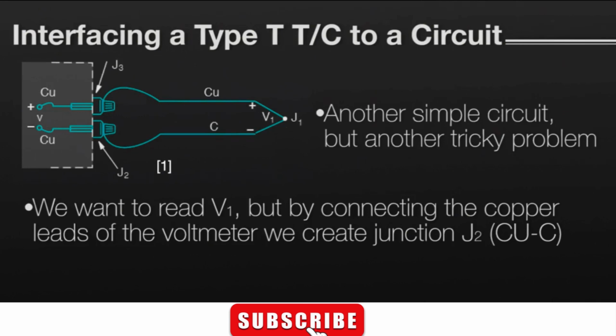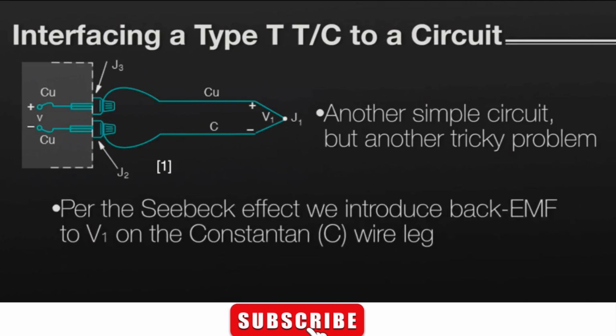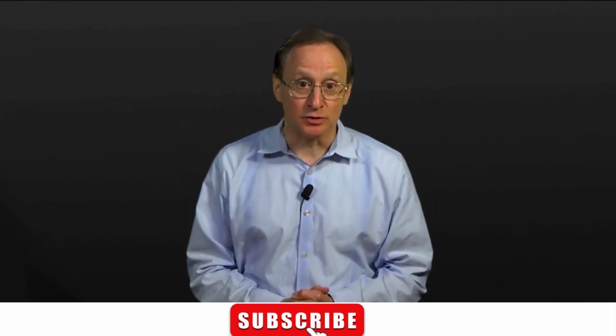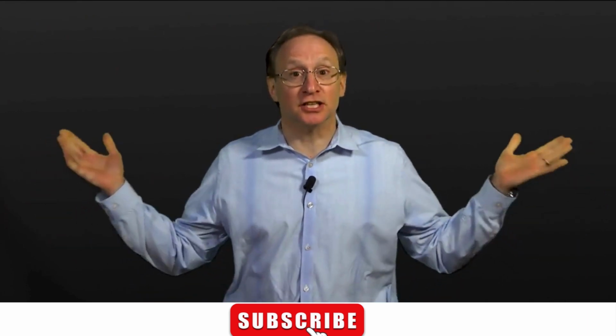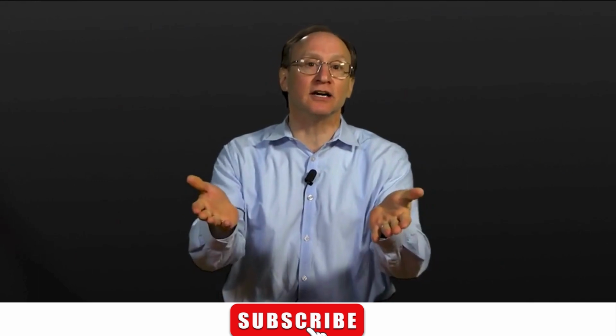We connected the copper and Constantan leads to the copper terminals of our voltmeter, and oops, we created another junction of dissimilar metals where the Constantan lead meets the copper terminal at junction J2. So what, you say? Well, here's what. You just introduced a back EMF thermoelectric voltage to V1 on the Constantan wire, and you can no longer correctly read V1. Oh no, you say. You have reintroduced doubt just when we thought all the doubts were cleared up with the RTDs.